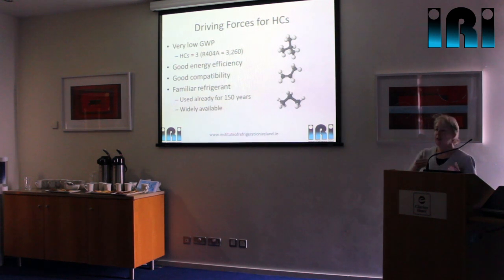You've got a very low direct impact. You've also got a low indirect impact because hydrocarbon systems tend to be more energy efficient. We've worked with many manufacturers of hydrocarbon appliances — they make an HFC range, they make a hydrocarbon range, and they measure the energy consumption of both. The energy consumption of the hydrocarbon range is generally somewhere between 10% and 20% lower doing the same job on HFCs. You've also got good compatibility — hydrocarbons are very good inside the system, compatible with the oils we use, with seal materials, gaskets, that sort of thing.